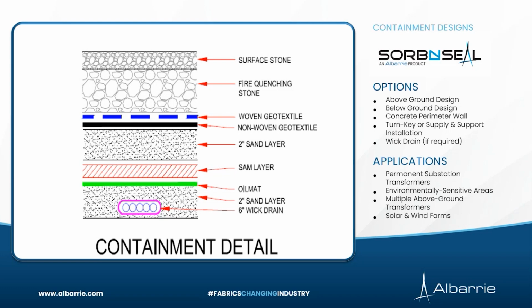So once we sort that out, we're going to build the containment. At the bottom of the containment, we're going to have our oil mat or oil blocking fabric. That's the one I showed you in the first video that will congeal and seal once you have an oil leak or spill. The super absorbent membrane, that's the white fabric I showed you in the second video, is referred to as the SAM layer, and that is installed over the mat. It will act as a sacrificial or protective layer to manage any chronic leaks that could happen over time in that containment system from any leaky equipment. That layer can be removed or replaced if required. So those are your primary filtration fabrics, okay?